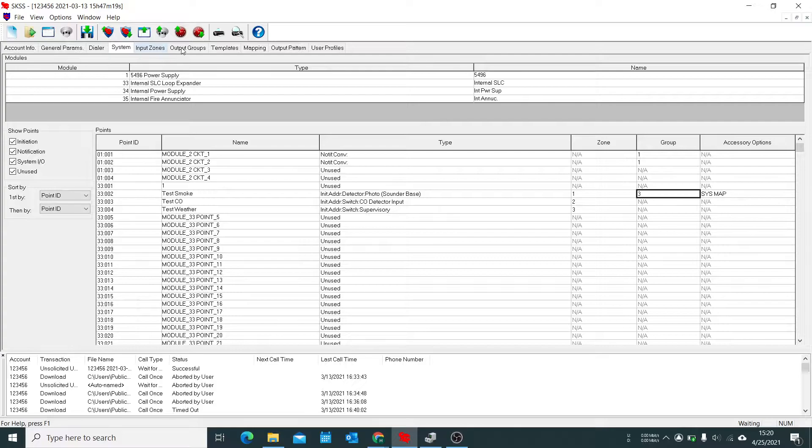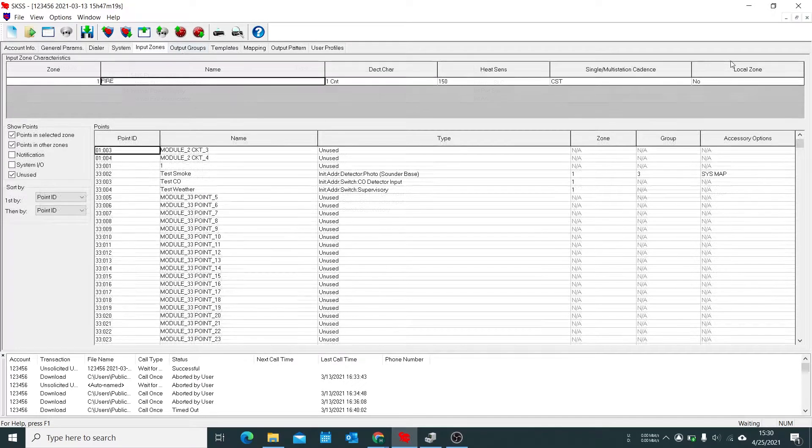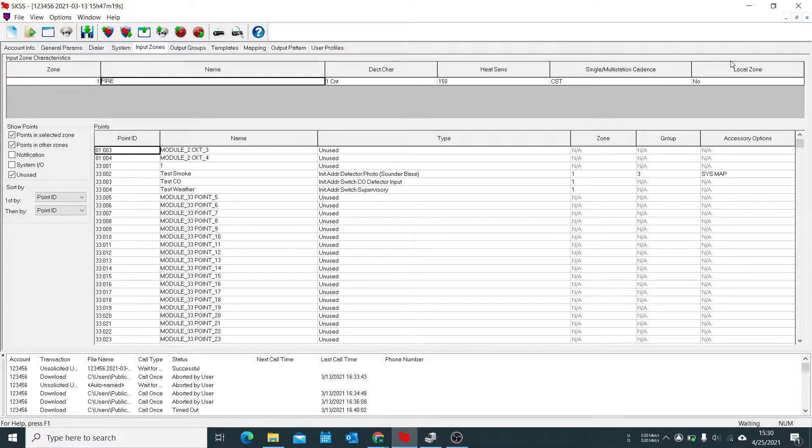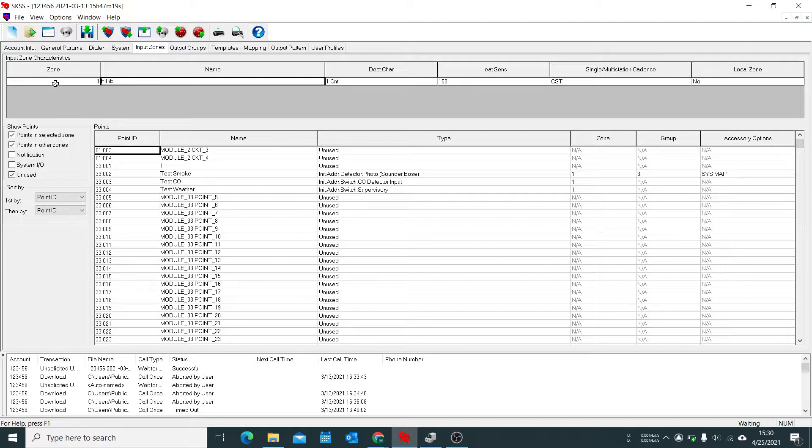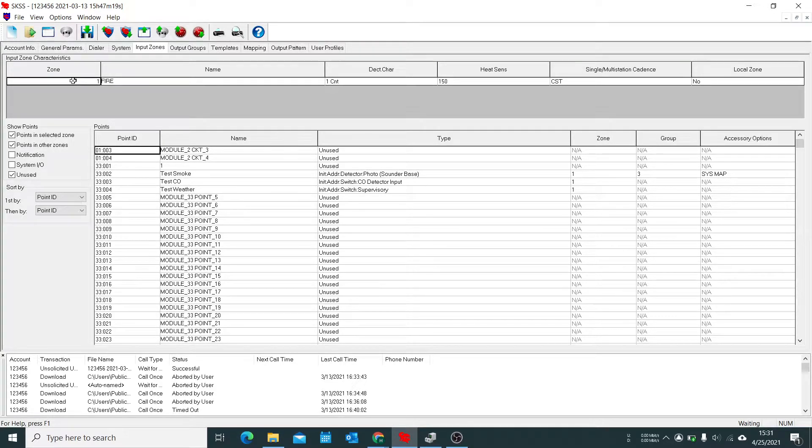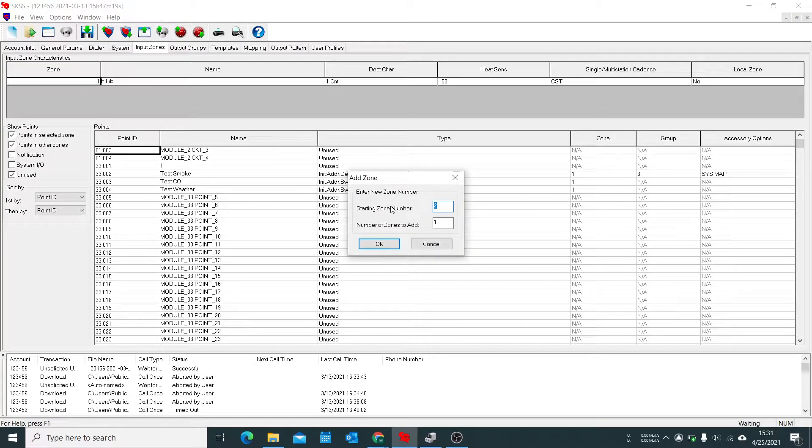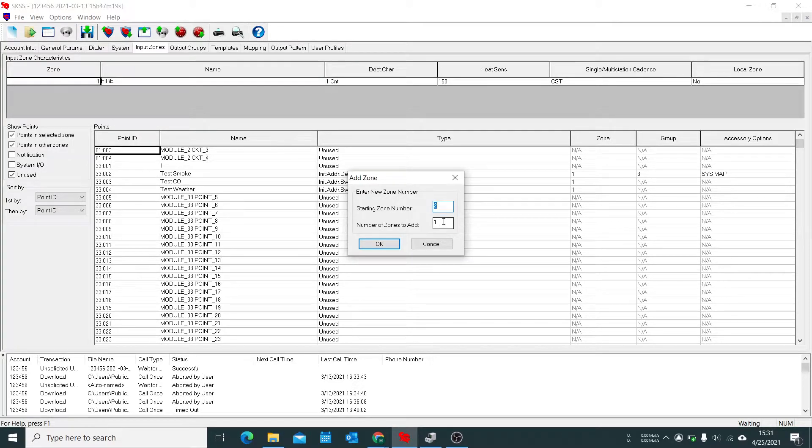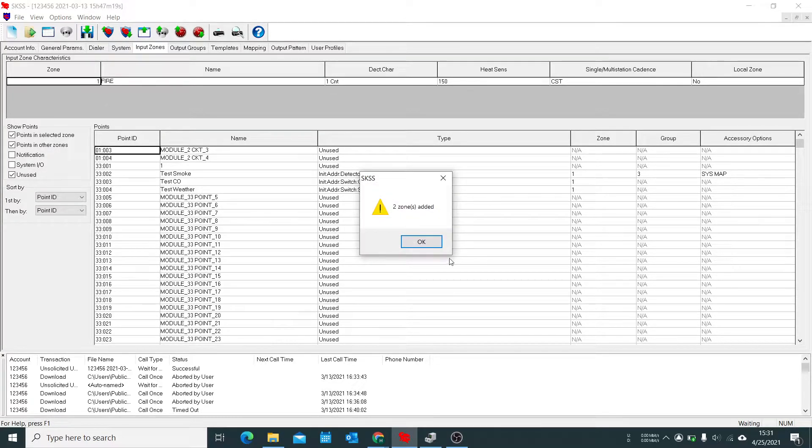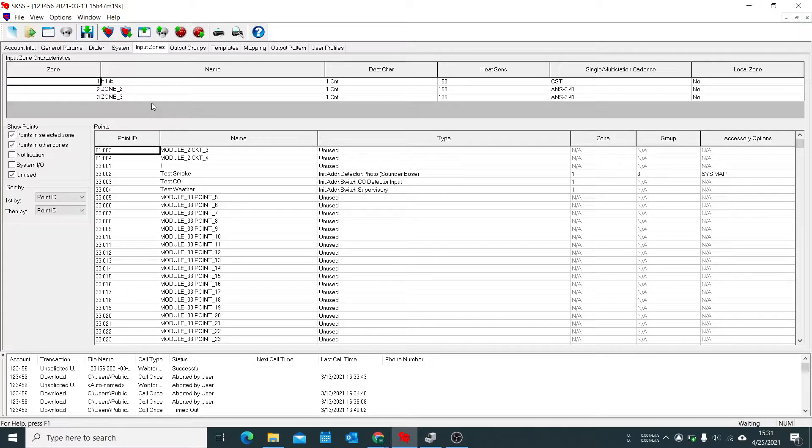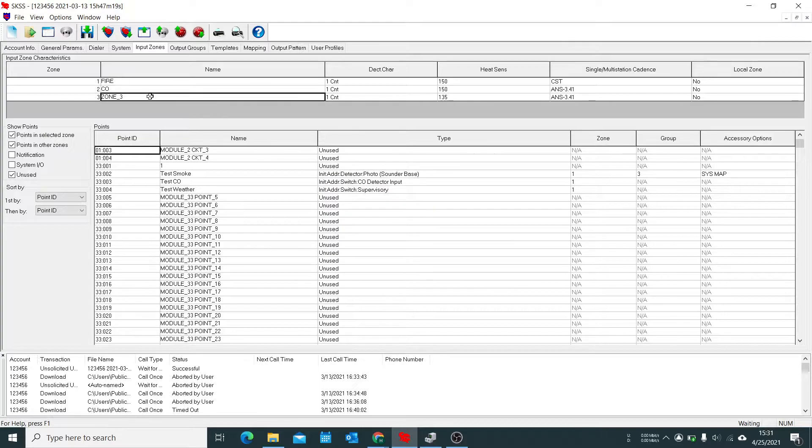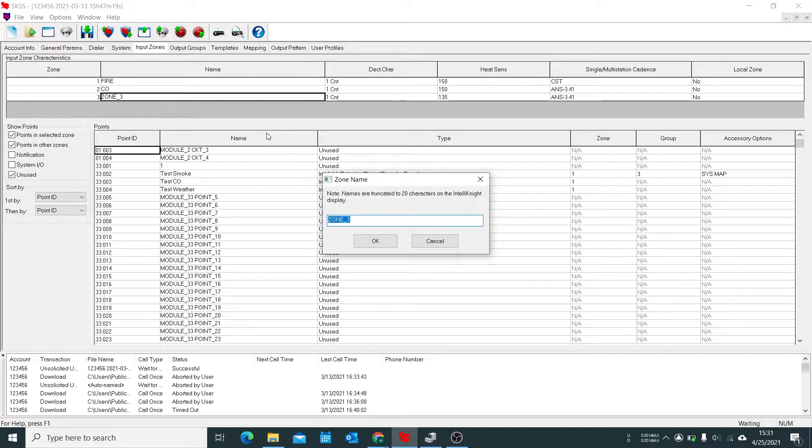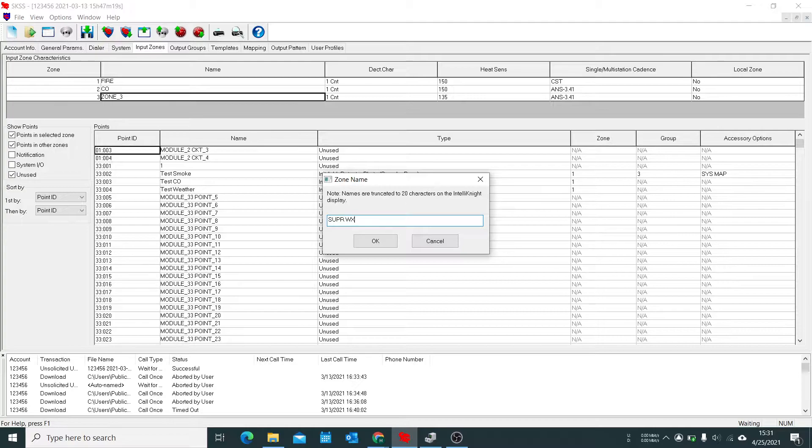So now we're going to go to output groups and program the rest. The first step in adding custom patterns and multi patterns to a sounder base is to first create a zone for each type of device event. So right now we have zone one which is fire and that's fine for a smoke detector. But we want to have a separate zone for our CO and our weather alert which is our supervisory. We're going to start at zone two and add two zones and then name them. We call one CO and the other one supervisory weather.